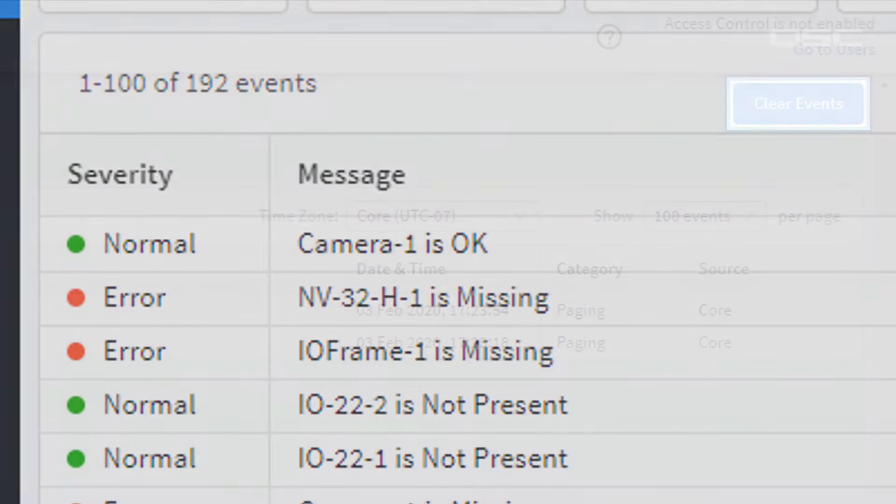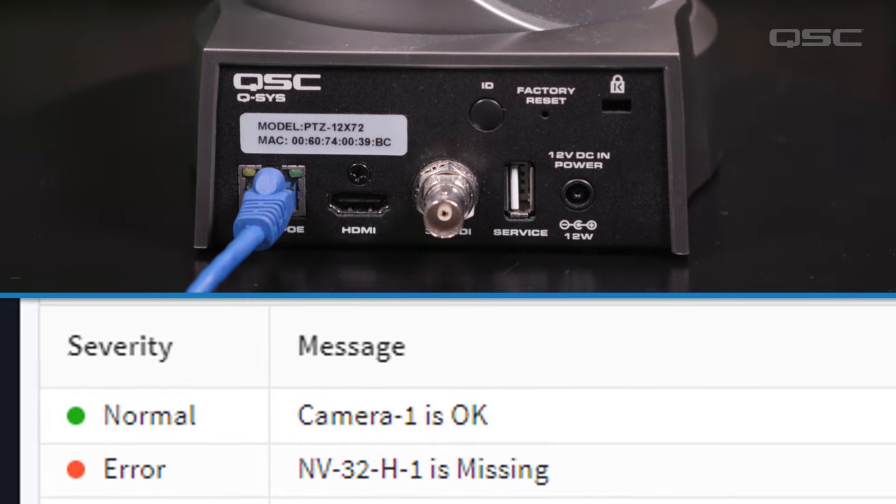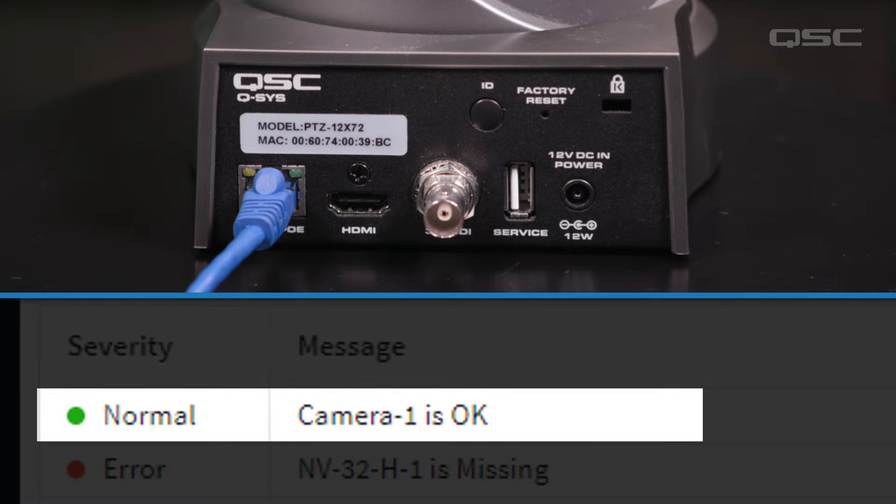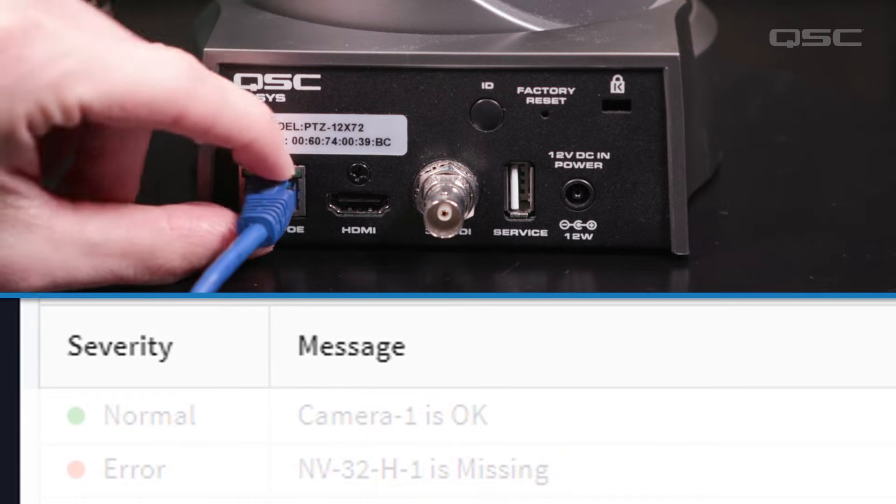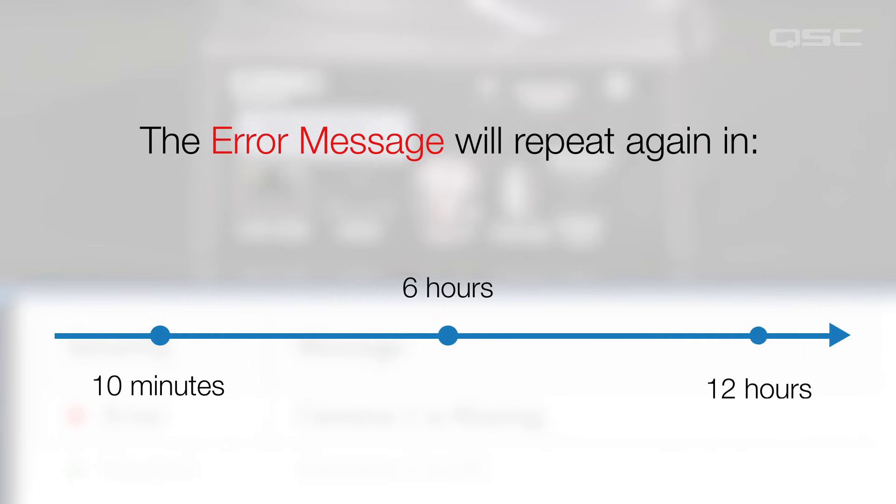Certain events in a log will repeat. For instance, if a device's status drops from OK, then an error message will log upon the first problem, and then repeat again in 10 minutes, then 6 hours, and then every 12 hours thereafter until the problem is corrected. The log will also specify how long the problem has persisted.